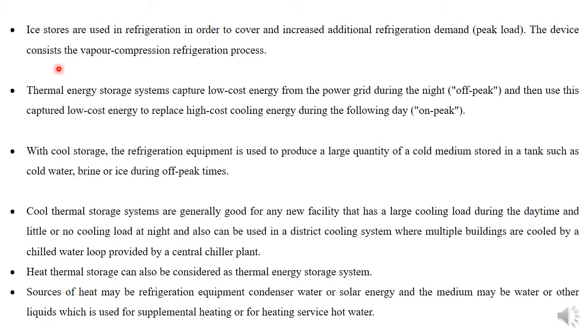The ice stores are used in refrigeration, like I said, to cover additional refrigeration demand during peak load. The device consists of a vapor compression refrigeration process. The thermal energy storage system captures low cost energy from the power grid during the night, which is off-peak time, and then uses this captured low cost energy to replace high cost cooling energy during the following day, which is on-peak. A large quantity of cool medium is stored in tanks, such as cool water or even brine, and it is converted to ice during off-peak times, and the ice will be used during on-peak time.